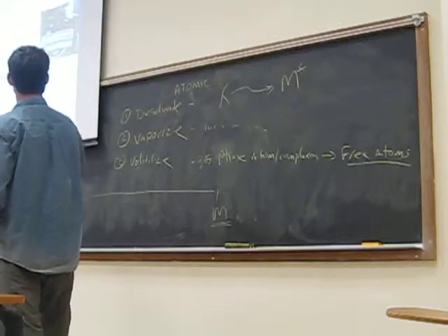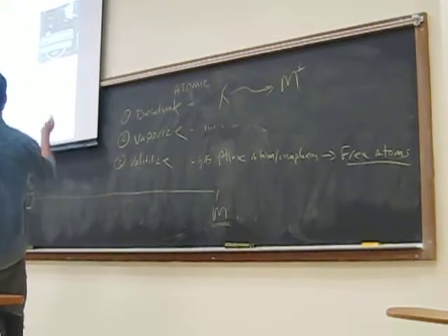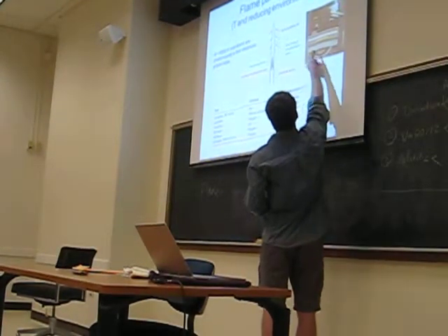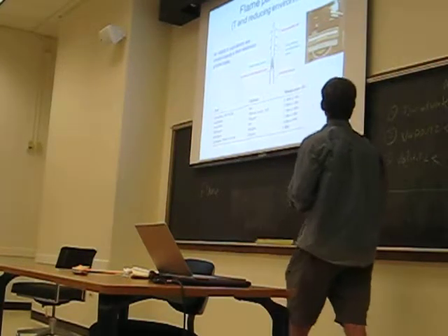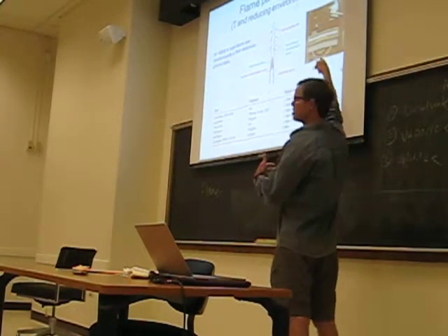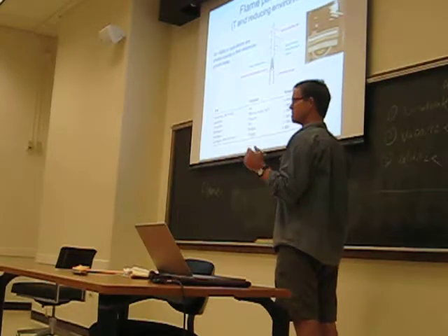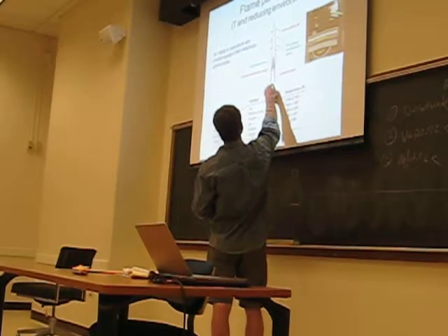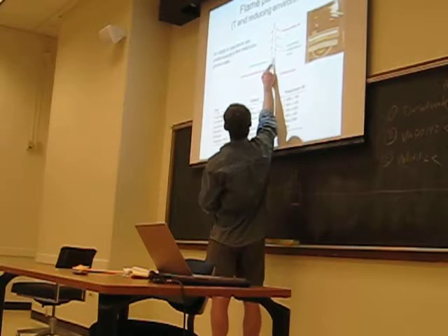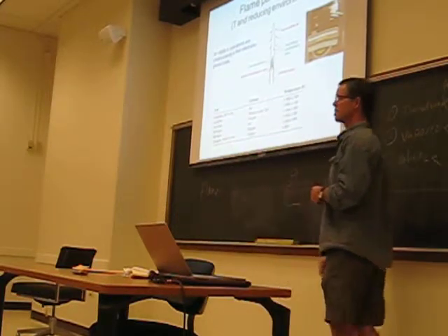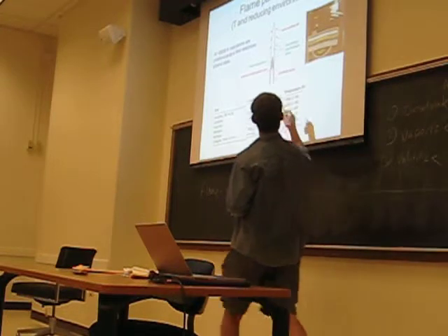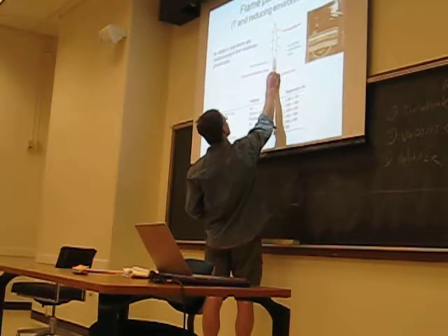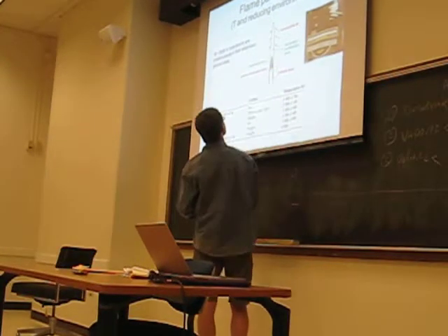So this is a little more detailed breakdown. We see this looks exactly like yours, right? And I made a point before that on this burner head, we had this slot, a millimeter in diameter, where the gas mixture comes out, and that little thing flips around and lights it for us, all automatically, which is very convenient. And then it burns away. And in the flame, if you were to do a cross-section of what that air acetylene flame looks like, you see that the flame contains a number of different zones of thermal gradient. This would be the burner head top right there, and then the flame is coming out, and it starts igniting here. You have these different zones of different temperatures.